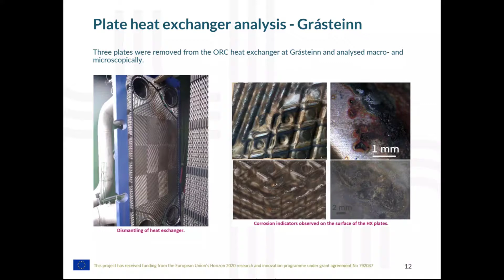To take the results together, for Grásteinn we observed corrosion on the heat exchanger plates, both in the form of pits, increased surface roughness, and some minor subsurface cracking. In general the heat exchanger plates did perform not badly, but a little bit under expectations, we could say. So it did not perform as well as expected, given the initial corrosion analysis of the coupons.